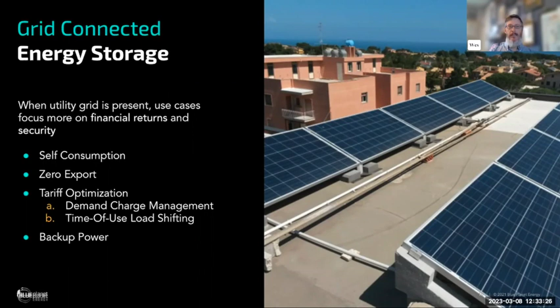This self-consumption is a common market application when you're connected to the grid. So sometimes utility companies will say, yes, you can connect your solar system to our grid, but you may not export beyond a certain amount. So here's the arrow showing just a typical grid connected solar system. And if you click it again, grid restriction is where the utility says, we don't want any of your solar energy exported onto our grid.